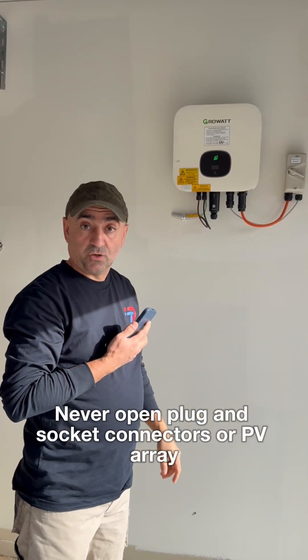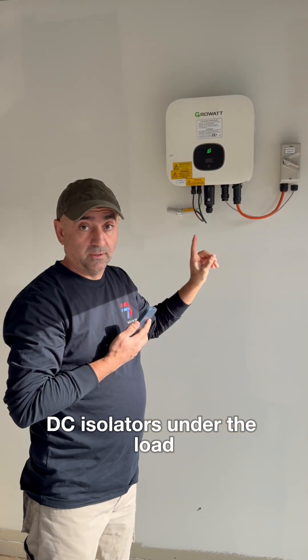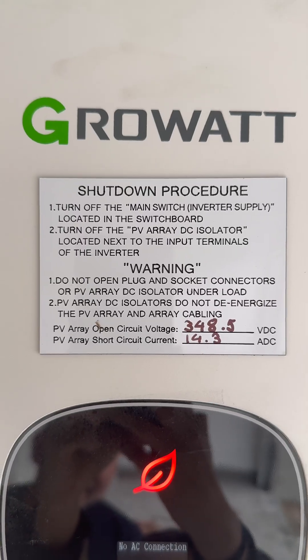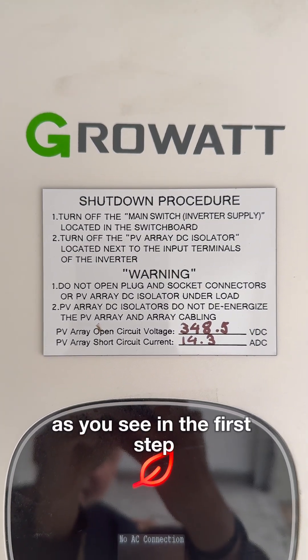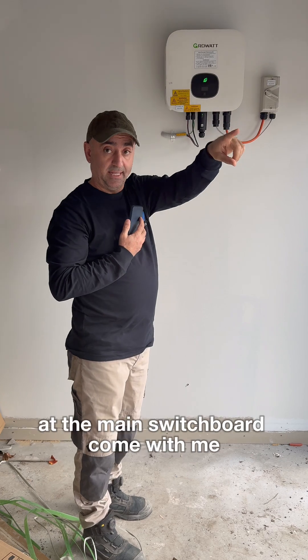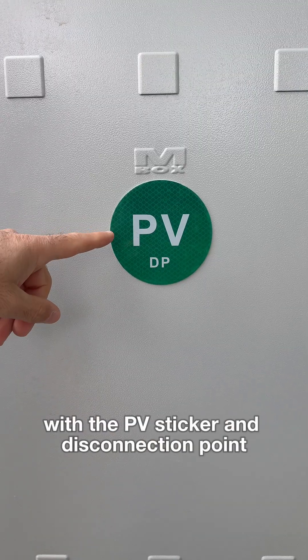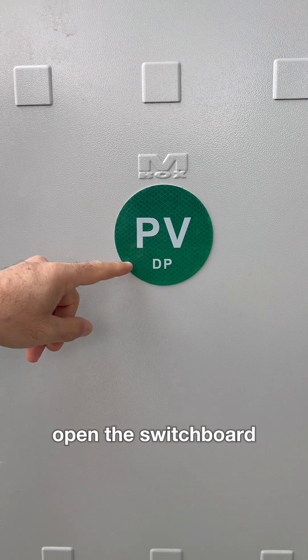Never open plug and socket connectors or PV array DC isolators under load. Always follow the shutdown procedure. The first step is to turn off the main switch inverter supply at the main switchboard. Come with me — this is our main switchboard with the PV sticker and disconnection point. Open the switchboard.